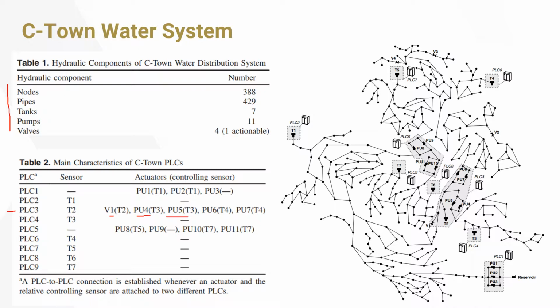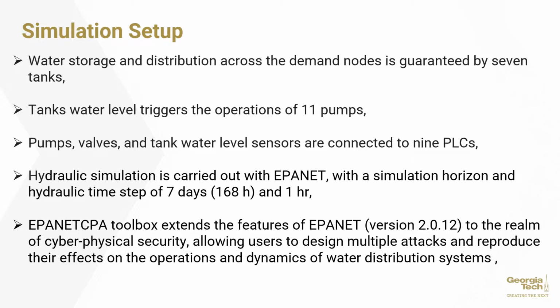And this is exactly what has been modeled through EPANET CPA, which basically takes care of the simulation part of those previously defined attacks. There are a bunch of simulation steps here. The first one is that water storage and distribution across the demand nodes is granted by 7 tanks. Tank water level triggers the operation of 11 pumps. Pumps, valves, and tank water level sensors are connected to 9 PLCs. Hydraulic simulation is carried out with EPANET with a simulation horizon of almost 7 days and a hydraulic time step of about 1 hour.